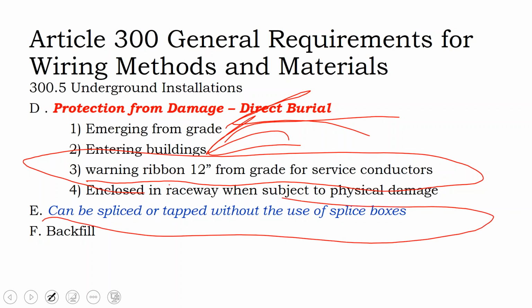Now, this is kind of interesting. In direct burial, you can be spliced or tapped without the use of splice boxes. So this is where you can find splice kits that are designed to be outside of a junction box, but that's because it's designed to be inside a direct burial wire run. That doesn't mean that you can take the same splice kit up on the rooftop, where it's not buried by ground, but exposed to metal parts. You can't just do a splice outside of a box under all circumstances, but you can in a direct burial.